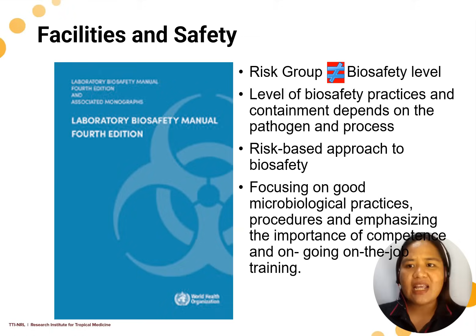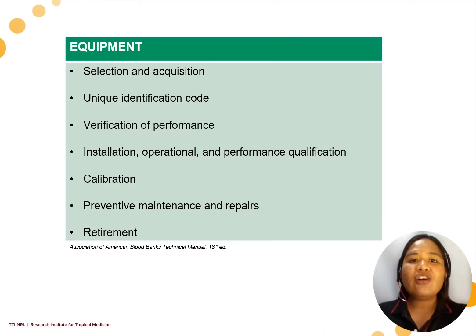And we also need to manage our equipment. So equipment must have proper selection and acquisition. You need to have your equipment with unique identification codes, verification of its performance. You have installation, operational, and performance qualification. And of course, updated calibration, preventive maintenance and repairs. And if your equipment would retire na, you also have a program for retirement, how you would dispose this, no? And make sure to have records of training and orientation of operation of our critical equipment for our technical staff.